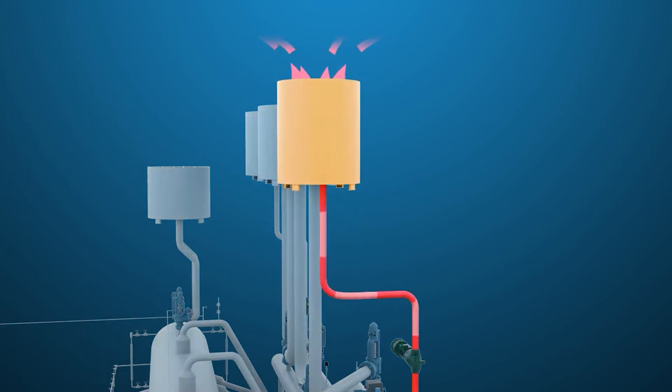There will also be a diffuser or silencer downstream of the valve that discharges to atmosphere to further reduce the noise. The valve will need to be sized with consideration for the silencer, as the silencer will create back pressure for the valve outlet.